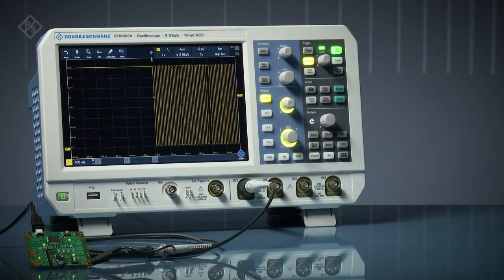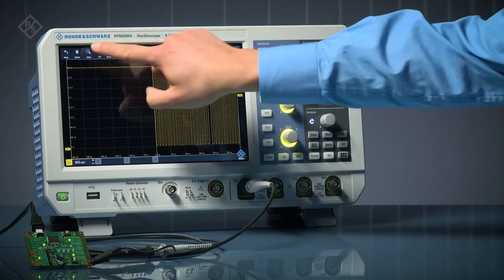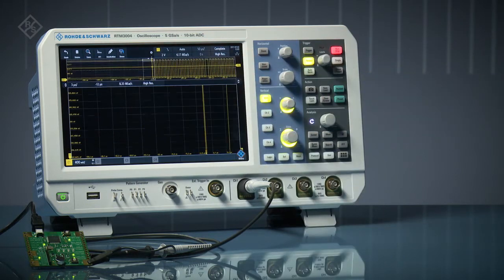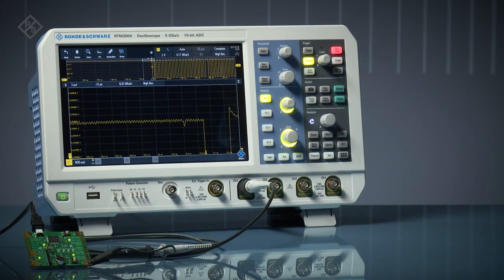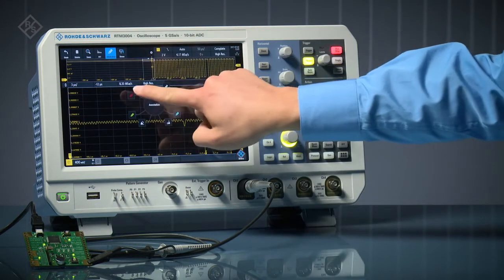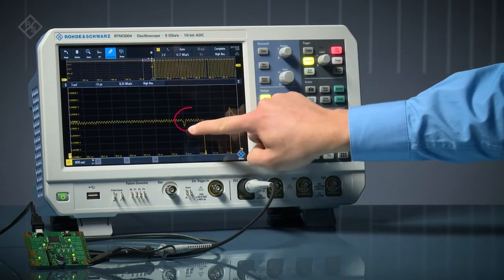Rohde & Schwarz RTM 3000 Series Oscilloscopes feature vertical zoom. Simply draw a box around the portion of the signal you want to magnify. Combined with the instrument's 10-bit ADC, vertical zoom allows you to find small signals in the presence of large amplitudes, like this one.